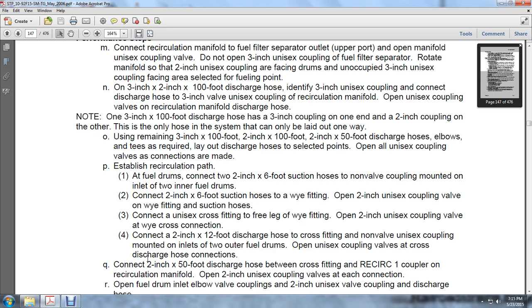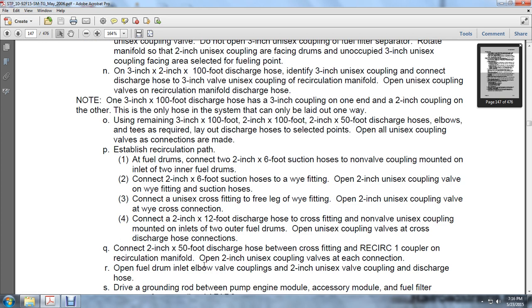Connect the 2-inch by 12-foot discharge hose to the cross fitting and to the non-valve unisex couplings mounted in the inlets of the two other fuel drums. Open the unisex coupling valves at the cross and discharge hose connection. Connect the 2-inch 50-foot discharge hose between the cross fitting and the recirculation coupler on the recirculation manifold. Open the 2-inch unisex coupling valves at each end. Open the fuel drum inlet elbow valve couplings and the 2-inch unisex valve coupling on the discharge hose.